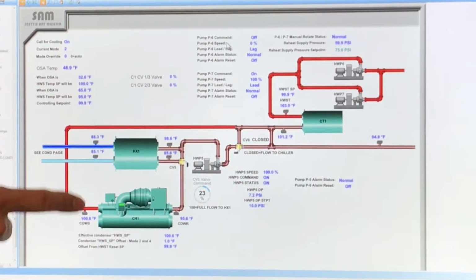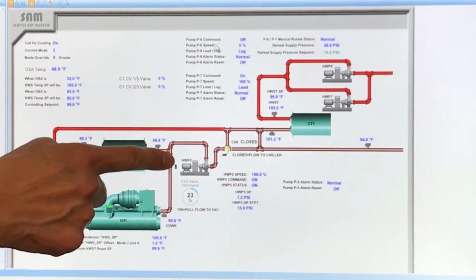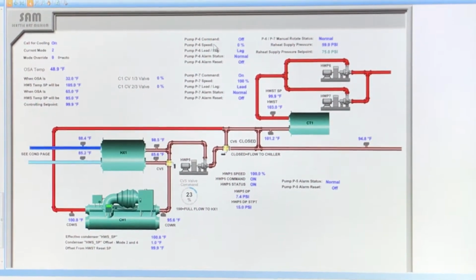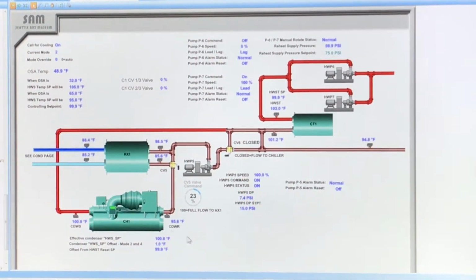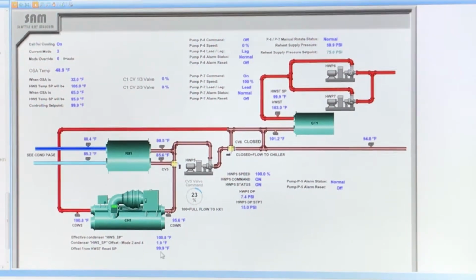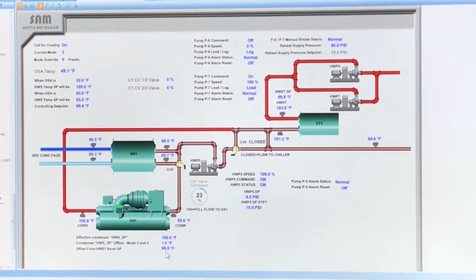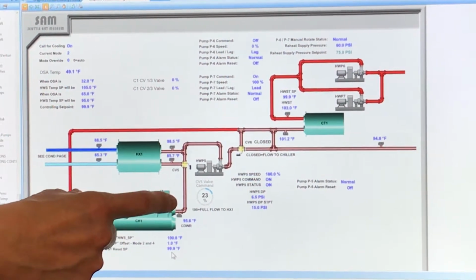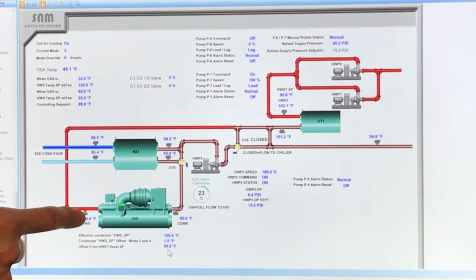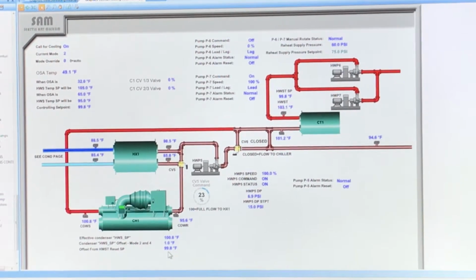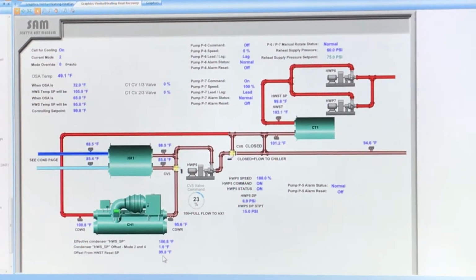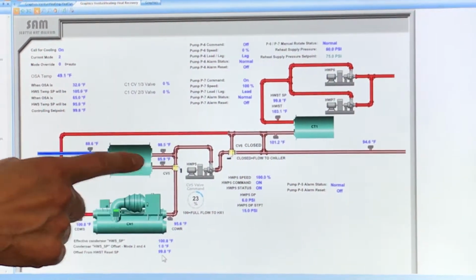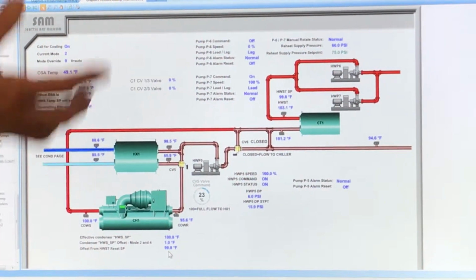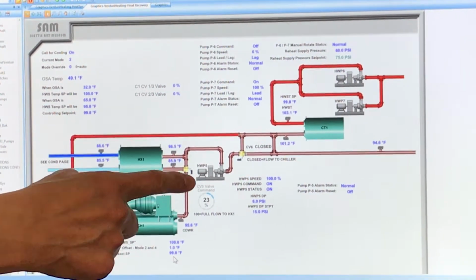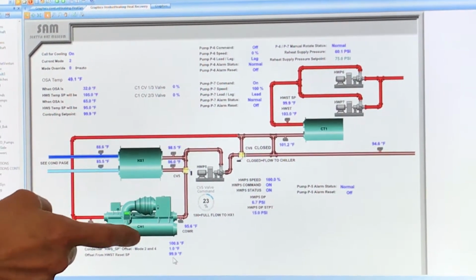So the tower is running, and you have the cold media here, and when you go through here, the temperature will drop when you pass through the heat exchanger, and this valve modulates based on that set point. You are trying to control the leaving condenser water set point so that it stays below a certain value, because the chiller doesn't like a high value, and when it gets above 110, you will be in trouble. Or when the delta T is so small that with 107 you are getting 105 on your return, you are also going to get some problem. So this valve will modulate open so that more water is going through the heat exchanger to cool down the loop and have a lower return to the condenser, so that the chiller will stay happy.